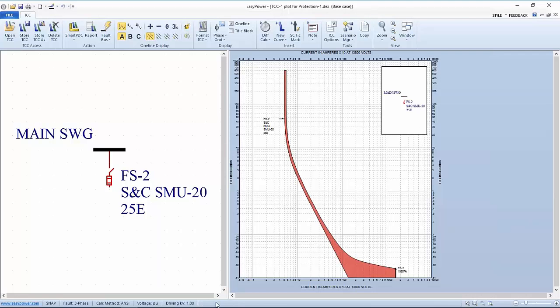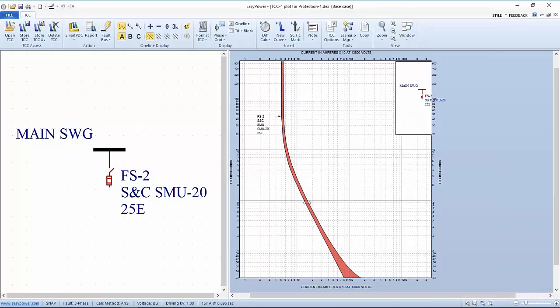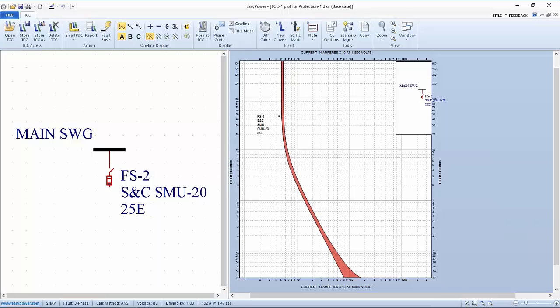The significance with a TCC curve is that we're displaying current on the horizontal axis and time on the vertical axis and it's at a log-log scale. The only difference between that and what we're used to in a typical Cartesian coordinate is the fact that we can get a whole lot more span of values. In this case, we're going from a tenth of a second to a thousand seconds all on one graph and consequently, we can expand or track the performance of a specific device over a wide range of current and time.